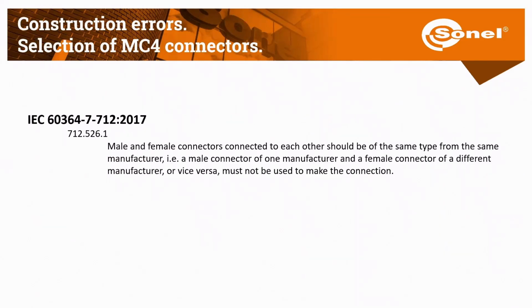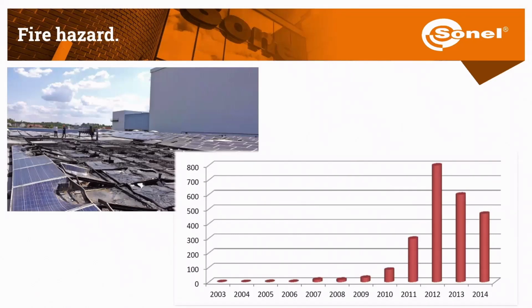Male and female connectors should be connected to each other on the same type and the same manufacturer, as I mentioned before. Male connector of the one manufacturer and the female connector of the different must be not used in such a connection. And from the very beginning, we see that that was the crucial thing in case of any fire hazard through the years. So when the real boom on the PV installation started in 2011, most of the fires were caused by improper connection of the connectors MC4, as we have the statistic made in Italy.